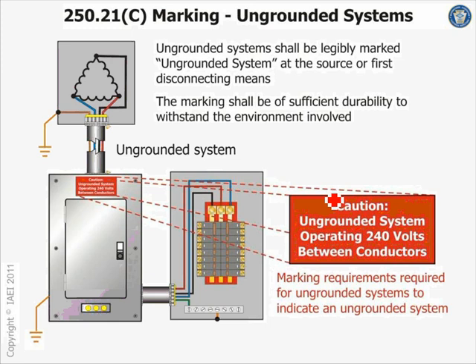So you have to identify the panels at the source, which is a transformer, or at the panel itself, telling the premises that this is an ungrounded system. If you're looking for a neutral, you're looking for something that does not exist. So don't keep looking.